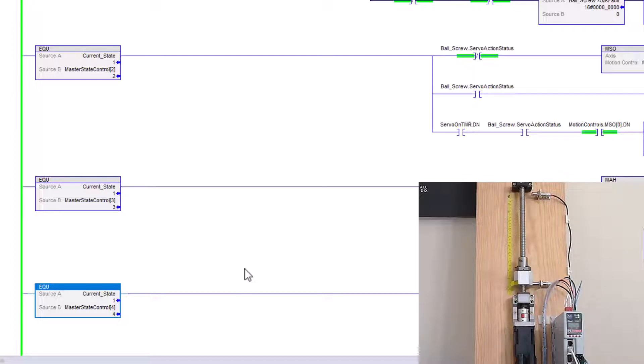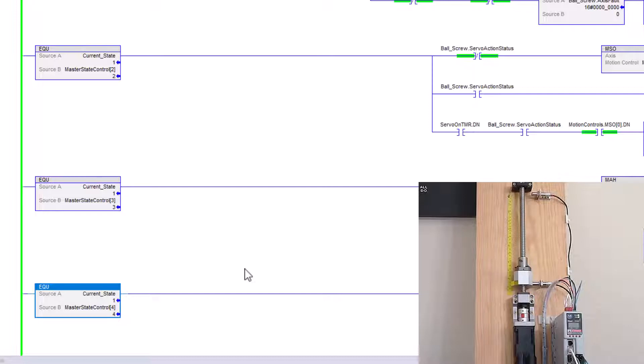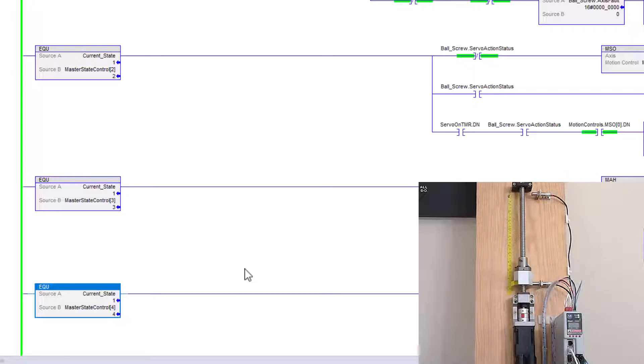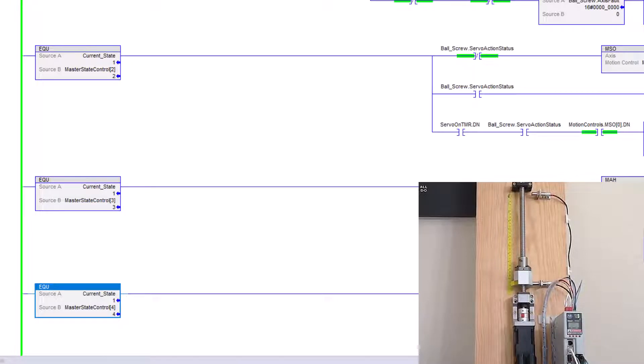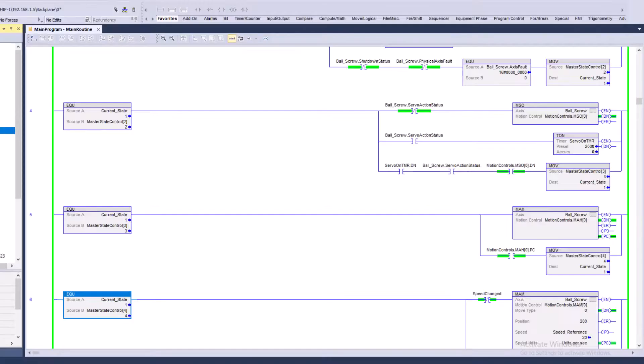But how I interpret that on my Kinetix 5500 is I have my common, which is my negative of my 24 volts, have my common attached to the common on the actual Kinetix 5500. A lot of people assume that you automatically get this control voltage from the Kinetix 5500, but you do not. So with all that said, let's go ahead, test the system and actually see how this actually works. I'm going to start the system real quick.